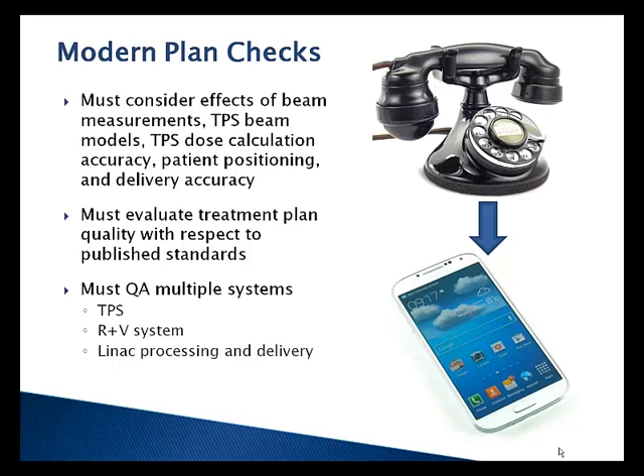So, what is a modern plan check? The title of the talk. It's something that when we're looking at this plan that's handed to us, as it goes down the line from dosimetrist to physicist to therapist, we recognize there are many systems at play. We recognize that the beam measurements had to be made correctly, the beam modeling had to be done correctly, dose calculation has some inaccuracy to it, patient positioning has some inaccuracy, and then the delivery is not perfect either. And we have to evaluate the plan knowing the basics of all of these components and make good decisions. And we have to QA multiple systems, the planning system, the R&V system, and finally the Linac.